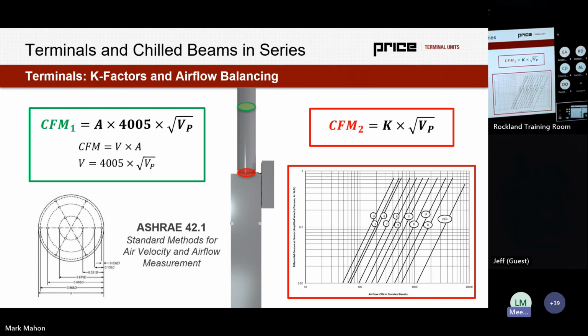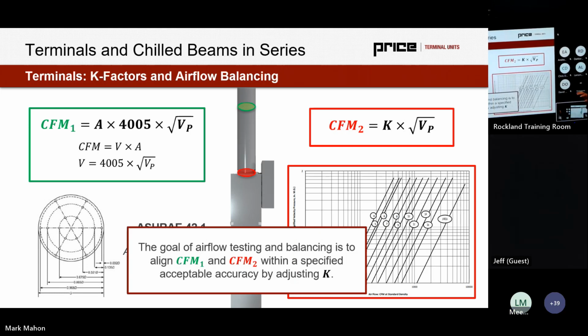They should be perfect if we have a perfect ideal inlet and if we're at standard air conditions, but I don't think those two things have ever actually happened at the same time on almost any job site. We're always a little hotter, a little colder, higher or lower pressure. We're going to have duct system effect and ducted conditions that are going to influence the way that we're measuring and controlling airflow due to localized velocity. So what we want to do is to align CFM1 and CFM2 within a certain specified acceptable accuracy by adjusting that K value, generally plus or minus 5%.